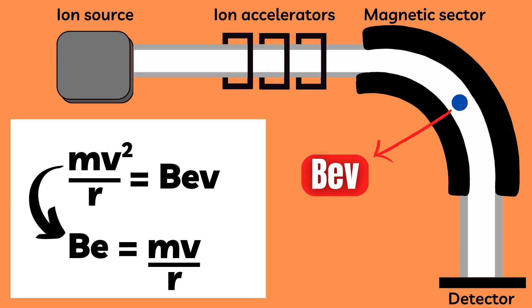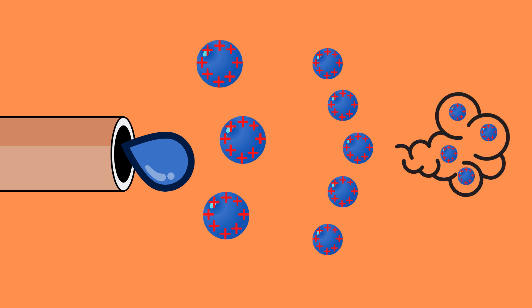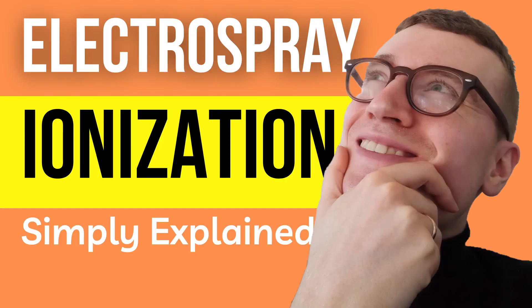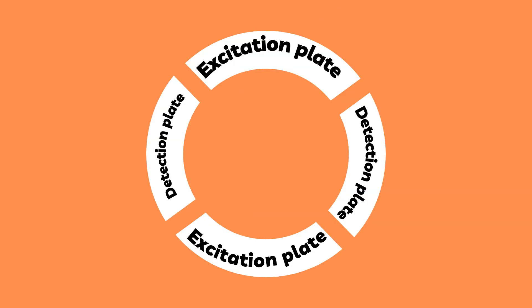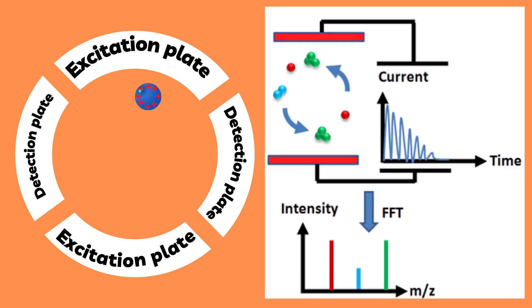Here is a simplified explanation of the FT-ICR process. A sample is introduced into the mass spectrometer and ionized, typically using electrospray ionization, which simply turns the sample into gas phase ions — electrospray ionization is something I discuss in greater detail in this video. The ions are then trapped in a magnetic field and excited by an RF, or radio frequency, field. The vibrational frequencies of the ions are dependent on the size of the ions and are measured using two detectors. The data is collected and analyzed using Fourier transform algorithms, which converts the vibrational frequencies into a mass spectrum that shows the relative abundance of ions at different masses.